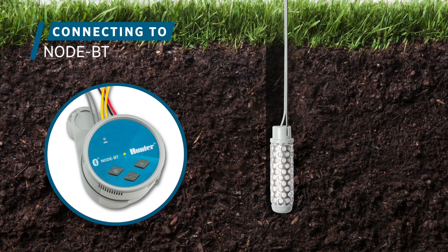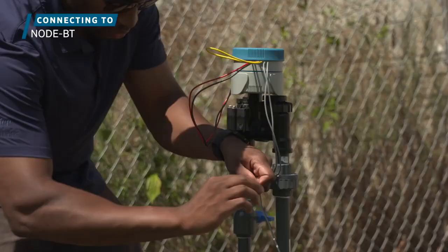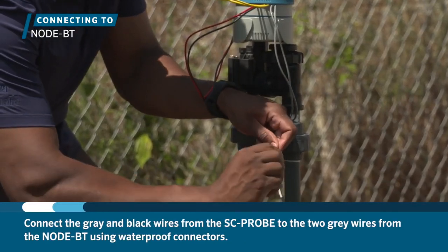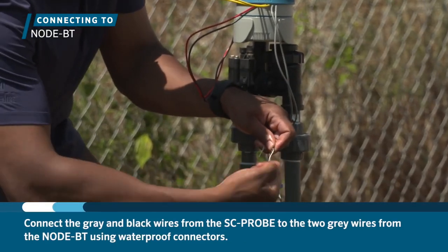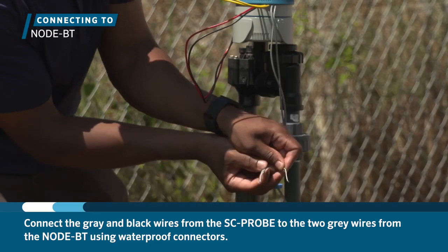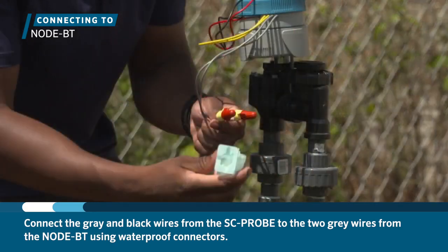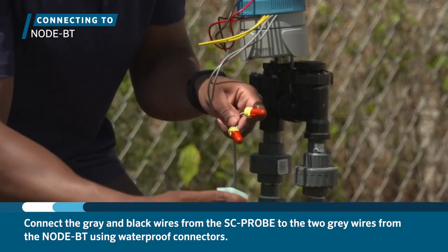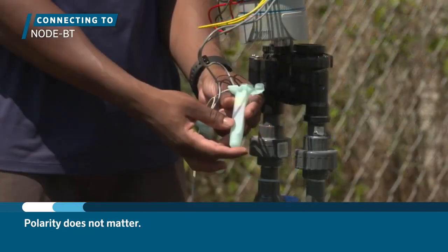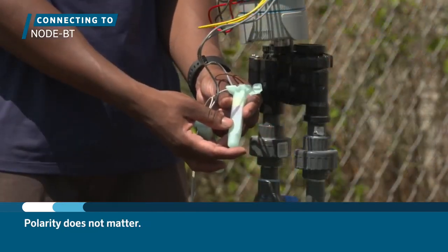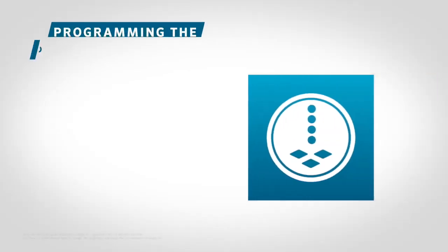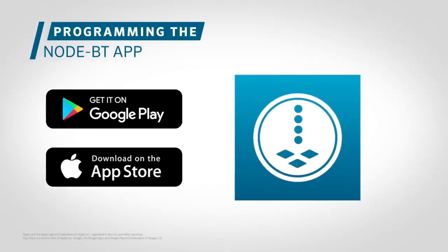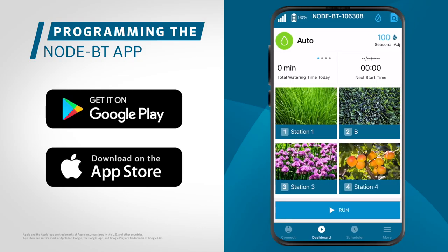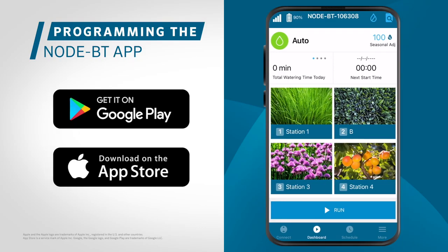Once the probe has been installed, you can connect it to the Node BT. Connect the gray and black wires coming from the probe to the 2 gray wires coming from the Node BT using waterproof connectors. Polarity does not matter. Once the Node BT has been connected and set up according to the directions, you can program the sensor.